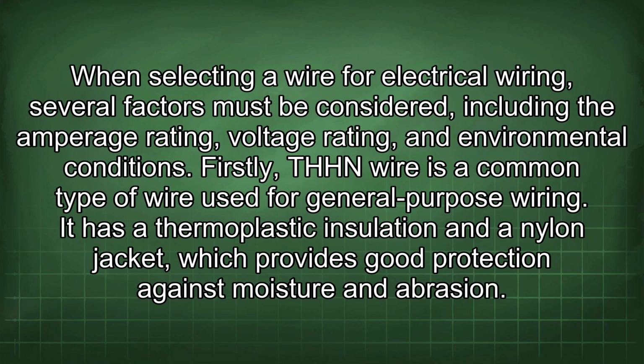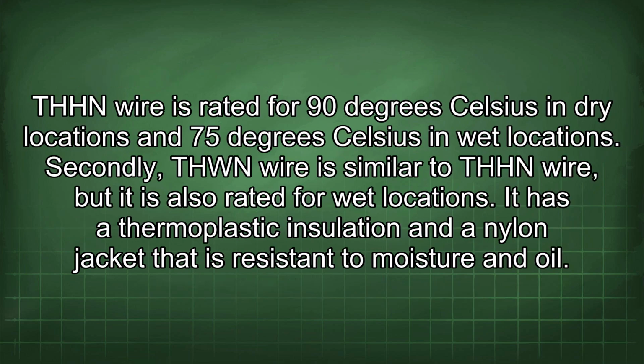When selecting a wire for electrical wiring, several factors must be considered, including the amperage rating, voltage rating, and environmental conditions. Firstly, THHN wire is a common type of wire used for general-purpose wiring. It has a thermoplastic insulation and a nylon jacket, which provides good protection against moisture and abrasion. THHN wire is rated for 90 degrees Celsius in dry locations and 75 degrees Celsius in wet locations.